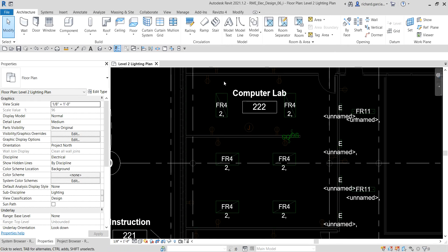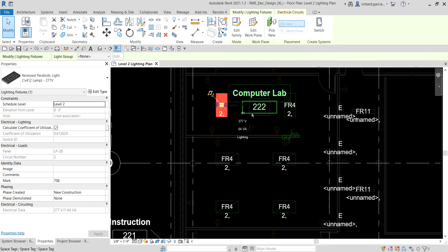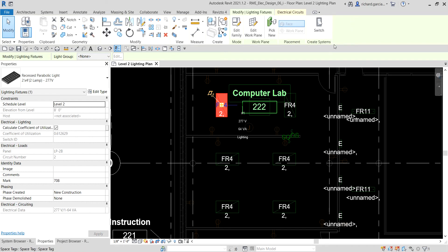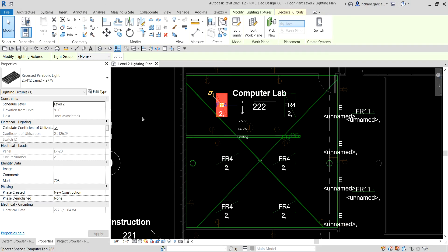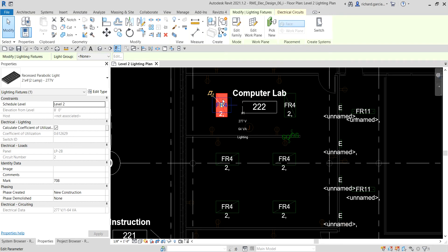To create the switch system, I'm going to select one of the lighting fixtures and then go to Create Systems. I have the Switch option here. Normally if a lighting fixture is not yet part of a circuit, you would see two options: Power and Switch. The reason there is no Power option here is because this fixture is already assigned to a circuit — panel LP2B, circuit number two. So we only have the Switch option since this fixture is not yet assigned to a switch.